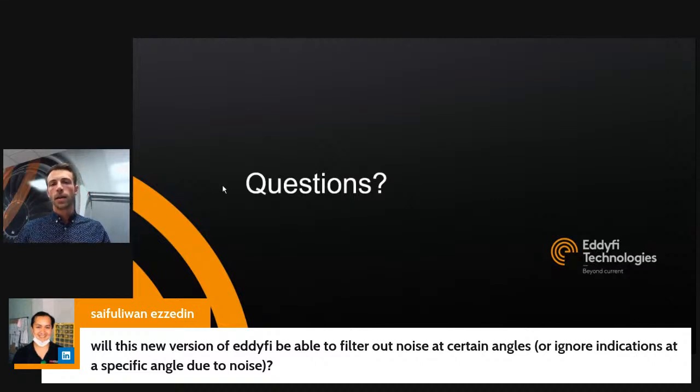For example, in your specific case and that noise level of the tube, you say any indications above 0.3 volts with a given phase range are non-relevant indications, then they will be grouped in that section. They will not be hidden, but you will be able to see those indications only in a group, and see the ones that are more important in different groups.